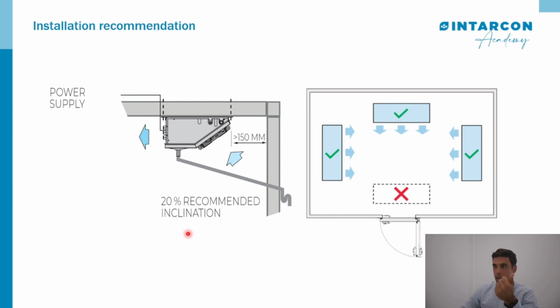For installation, this recommendation is for each low profile evaporator, not only for propane evaporators; it's a general recommendation for every evaporator or air cooler that you could install in a cool room. Ensure the direction of the airflow. It's recommended that the air be blown lengthwise in the room, close to the door, mainly to avoid condensation of the entry air and also to avoid blockage due to freezing air. This unit should also be placed at the end of the cool room, and the inclination of the drainage should be higher than 20%.